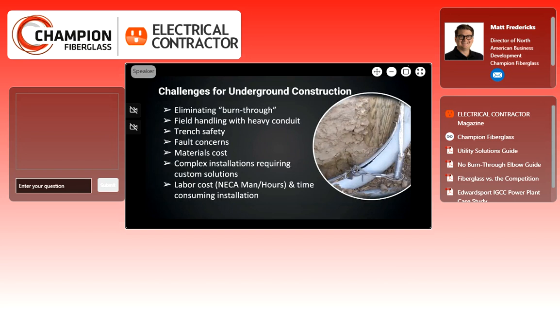Fault concerns are another thing to consider. If you have a cable fault on the inside of metallic conduit after the install goes, this would be for really the maintenance and operational part of underground construction. That cable will actually weld to the inside of metallic conduit. And if a fault occurs in PVC conduit, it will actually melt to the inside. I will mention that fiberglass conduit is not affected by cable faults. So that is a consideration when you're installing underground cable in conduit. You want to make sure that it's in a fault-resistant conduit.